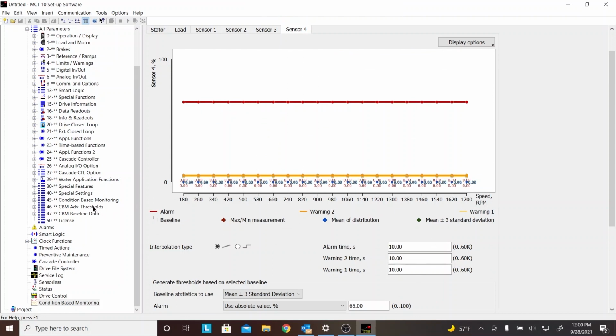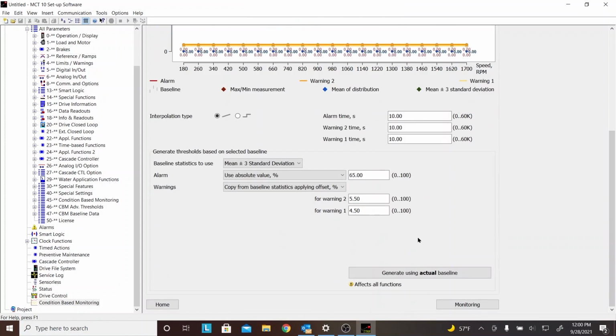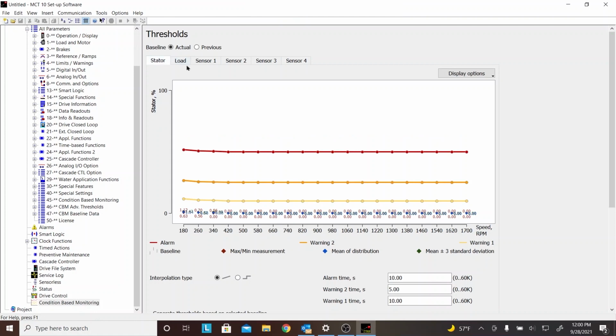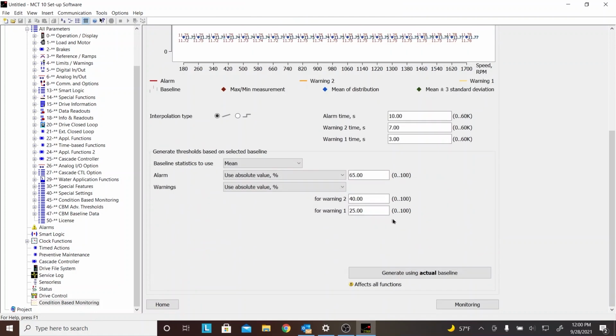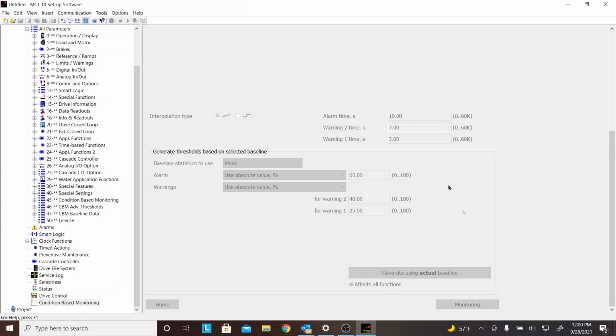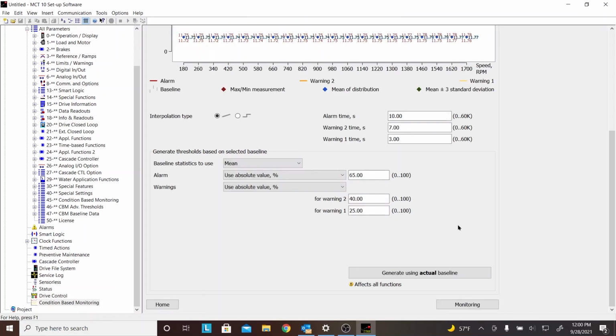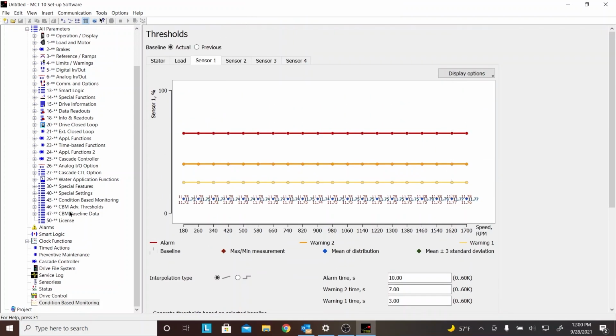Now, we have set the thresholds, and over on the left here, those thresholds in group 46 have been loaded. The baseline has been loaded in 47, and we're about to go into the monitoring phase. But before we do anything, to make sure those are all set and all the envelopes are filled up and programmed properly, we would want to go down and generate all those values into the actual baseline program so we can have everything there comparing against the baseline. So now that we've done that, all these groups over here are filled up with the right data.